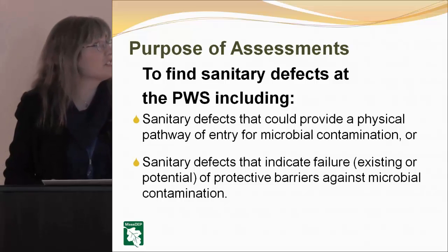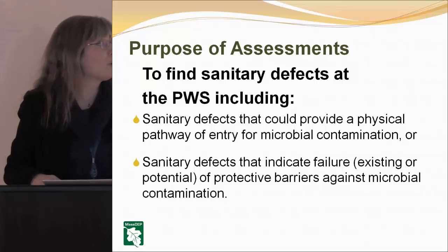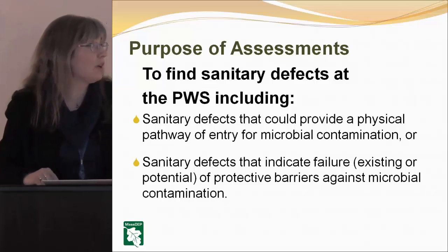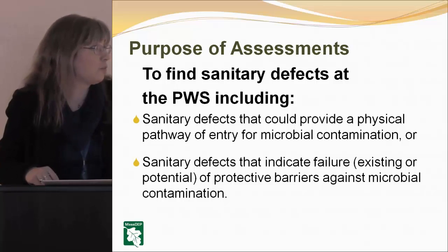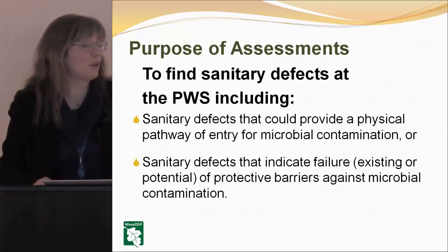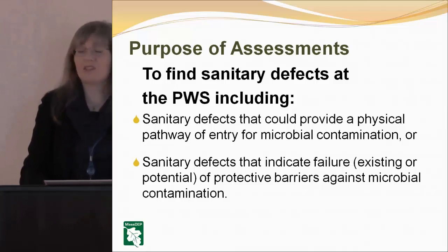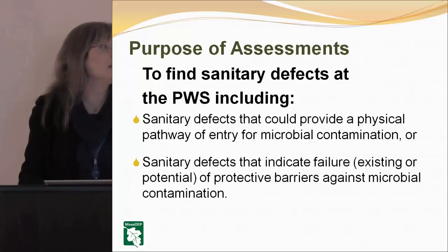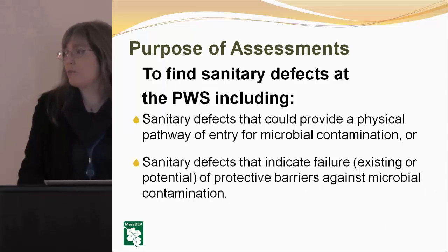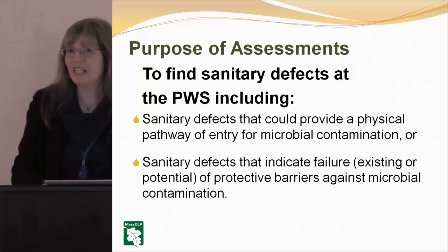Are there any sanitary defects that could provide a physical pathway of entry for microbial contamination, or sanitary defects that indicate a failure of protective barriers against microbial contamination? When you had the total coliform detect, did you go out and see if somebody ran into your wellhead with a lawnmower? The landscaping guys came by and they whacked it. Is your cap still there? Is there a crack in the casing?